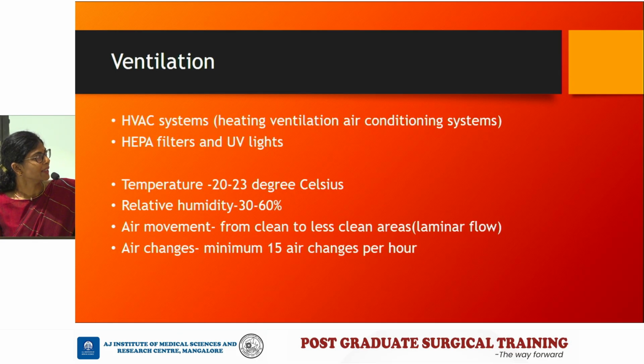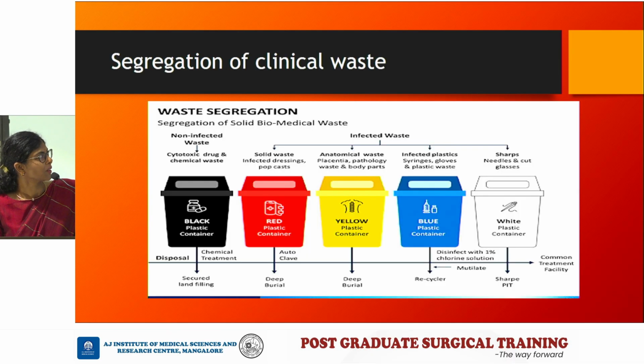Coming to ventilation, many OTs are fitted with HVAC systems, but some have split ACs, which need to be cleaned every month. What you need to observe is whether the temperature is maintained between 20 to 23 degrees Celsius and a relative humidity of around 30 to 60%, with about 15 air changes per hour.